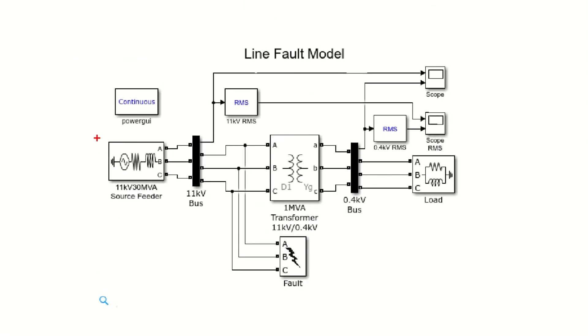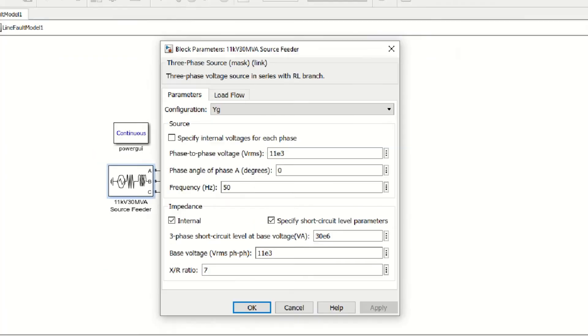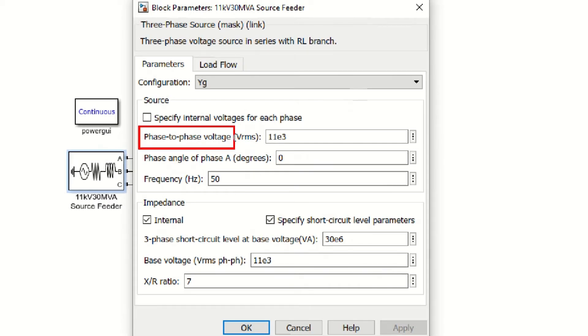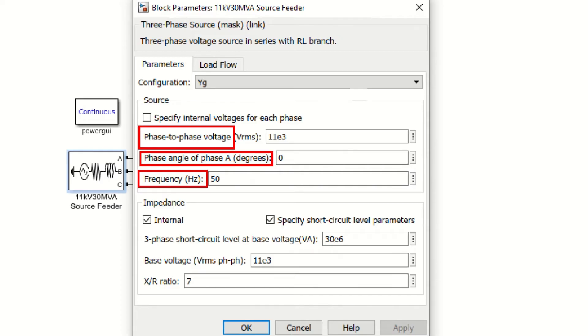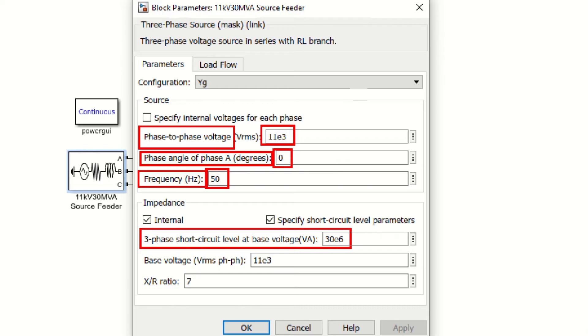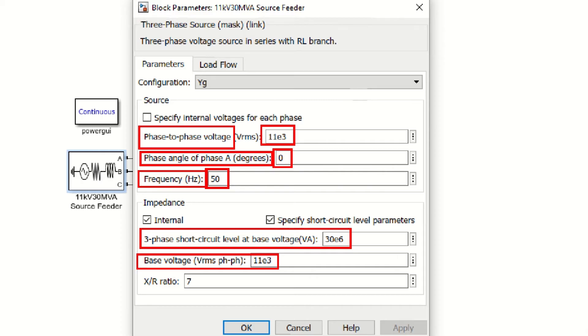It may be noted that this model contains the three-phase voltage source block as shown here. Double-click on it to see its values. In the parameters section, first data consists of phase-to-phase voltage, phase angle, and frequency. As we are using the distribution system, the common sending end line voltage is 11 kV, therefore 11 kV is used. In the impedance parameter section, base MVA is chosen as 30 MVA, base voltage is chosen same as that of the original voltage which is 11 kV, and the X upon R ratio is chosen as 7, which is the default value.